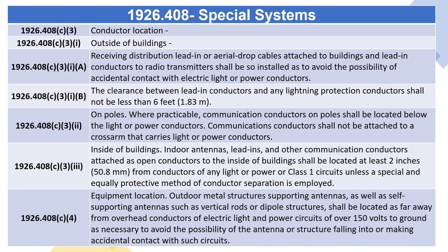1926.408(C)(3)(iii) — Inside of Buildings. Indoor antennas, lead-ins, and other communication conductors attached as open conductors to the inside of buildings shall be located at least 2 inches (50.8 millimeters) from conductors of any light or power or Class 1 circuits, unless a special and equally protective method of conductor separation is employed. 1926.408(C)(4) — Equipment Location. Outdoor metal structures supporting antennas, as well as self-supporting antennas such as vertical rods or dipole structures, shall be located as far away from overhead conductors of electric light and power circuits of over 150 volts to ground as necessary to avoid the possibility of the antenna or structure falling into or making accidental contact with such circuits.